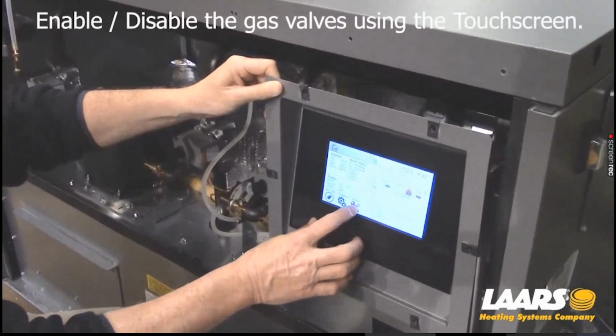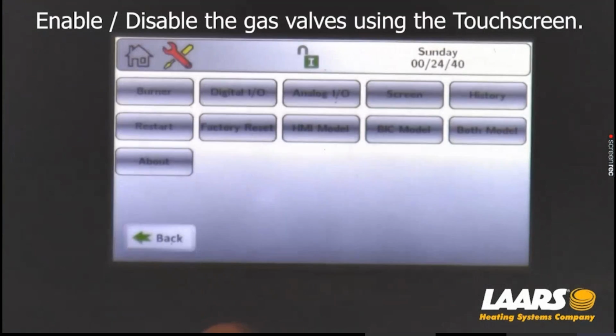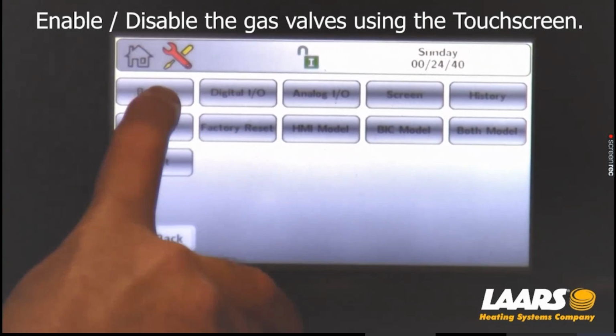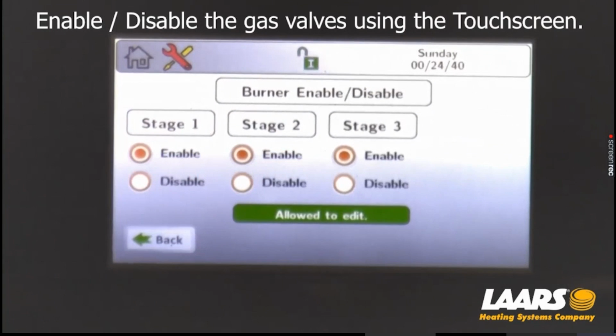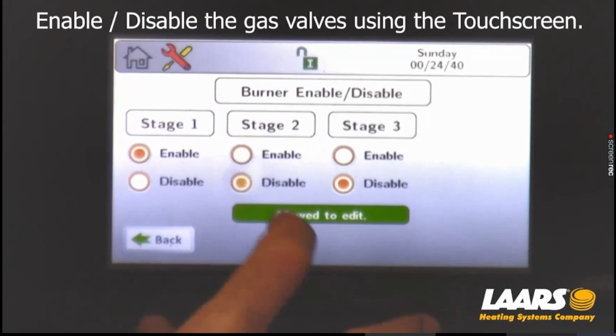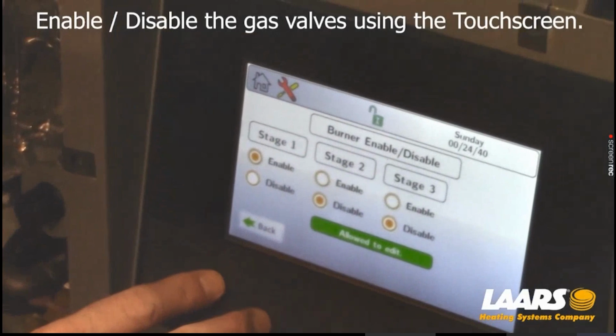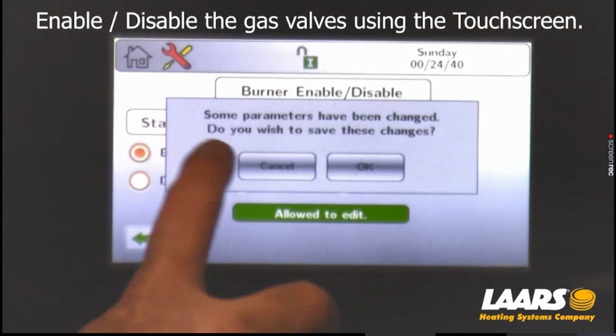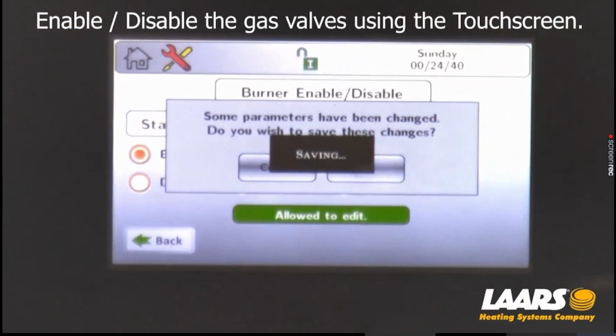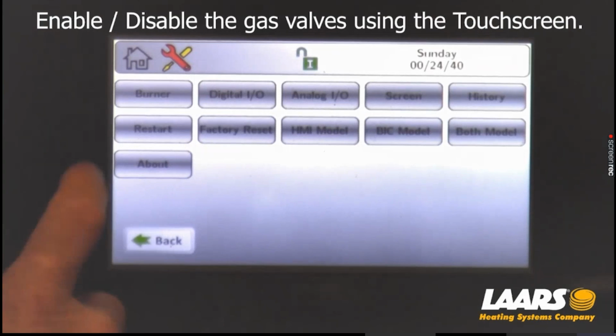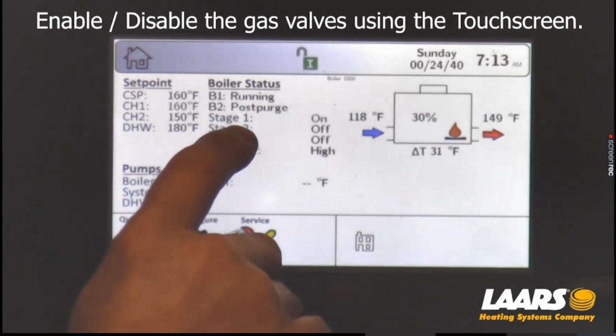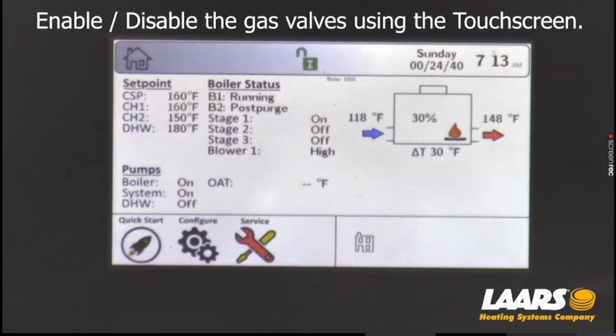So the digital way, we'll go in under service, press service, and the first option here is burner. Press burner. And this boiler is a 1 million, so I have 3 stages. If you have a 2 million, you're going to have 4 stages, etc. Maybe only a 500, a 750, only have 2 stages. So we can go in and shut off each stage. For this example, I'm going to shut off stage 3 and stage 2 to check my manifold on stage 1. Once I press disable, press the back button. It's going to prompt you to choose OK. Press OK. And now I'll go back to my home screen, and you'll see that stage 2 and stage 3 is off. Only stage 1 is on.